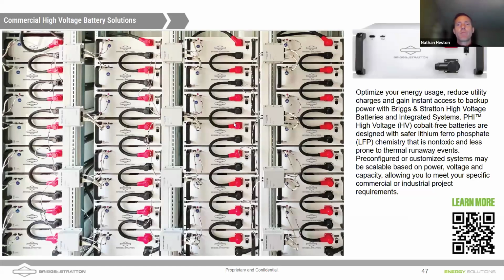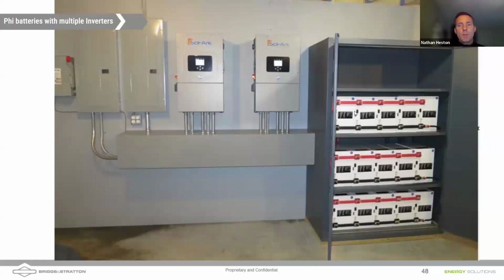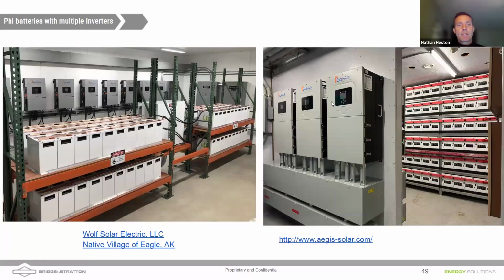Here's an example of a high voltage system. So we've got a very large number of high voltage projects across the country. We have the ability to integrate with different inverters, including the Sol-Ark inverters, but also the Outback inverters that are not hybrid inverters. So they're not designed to bring solar in, but if you're just looking at a strictly battery-based backup system, you can use those. Here's an example of bus bars being used. It's nicely shown that they're pulling power off of opposite corners of the bus bars. That's best practice to keep the battery system balanced.